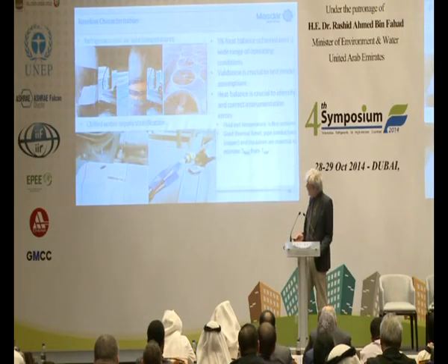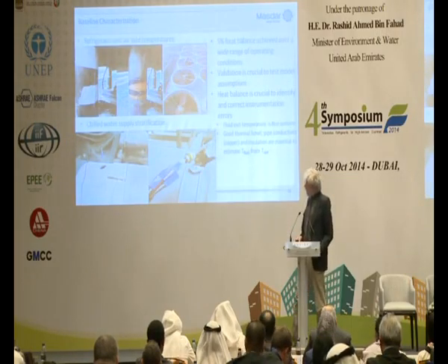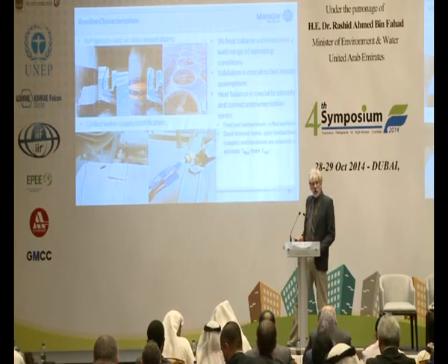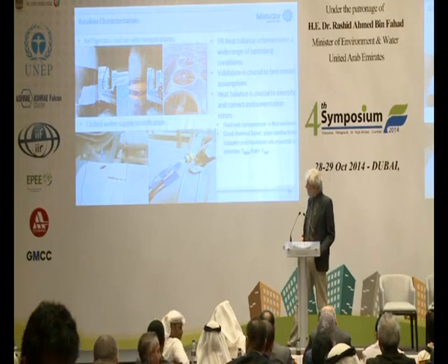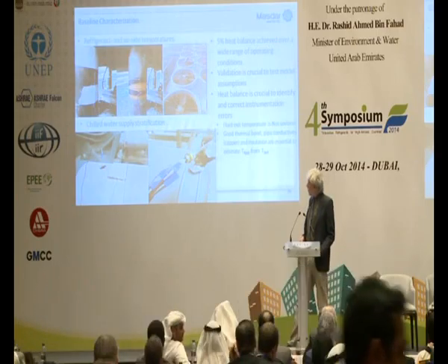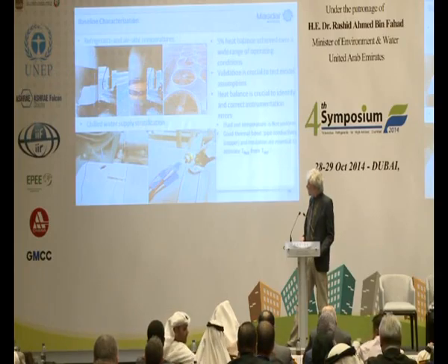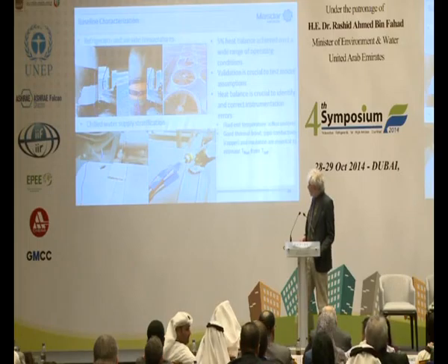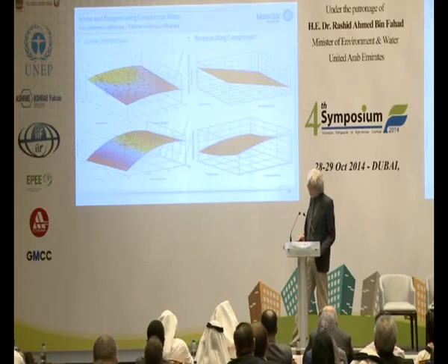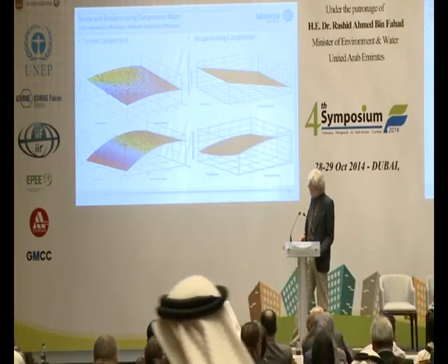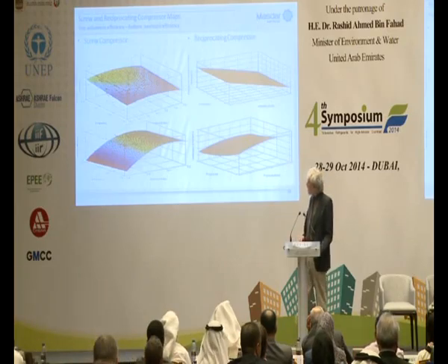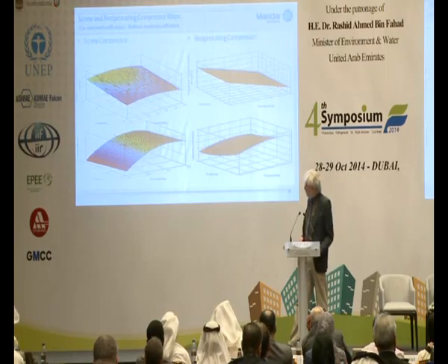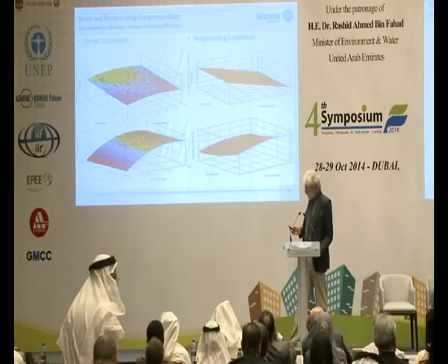So just move back. Now let me return to the modeling. The evaporator and condenser can be modeled quite accurately based on engineering principles. We use effectiveness NTU models with a moving phase boundary. And these we're able to validate from the measured data. The compressor is another story, and in particular on this machine, we have an economized screw compressor. Our initial efforts have been to operate the machine over a wide range of conditions. This is a variable speed screw compressor, runs from about 40 to 200 hertz shaft speed. And each compressor has two models.